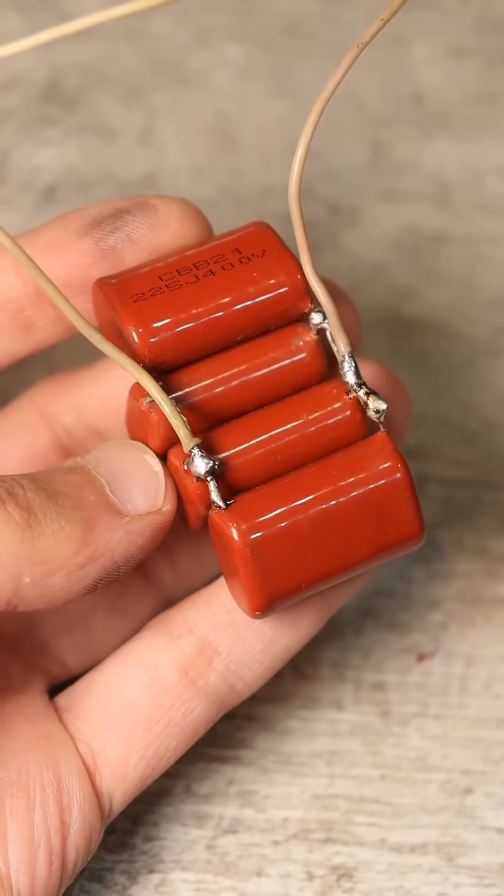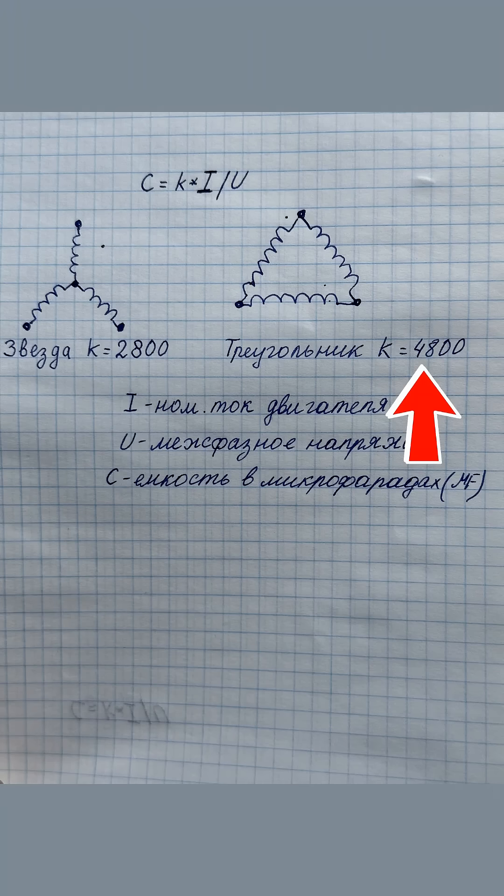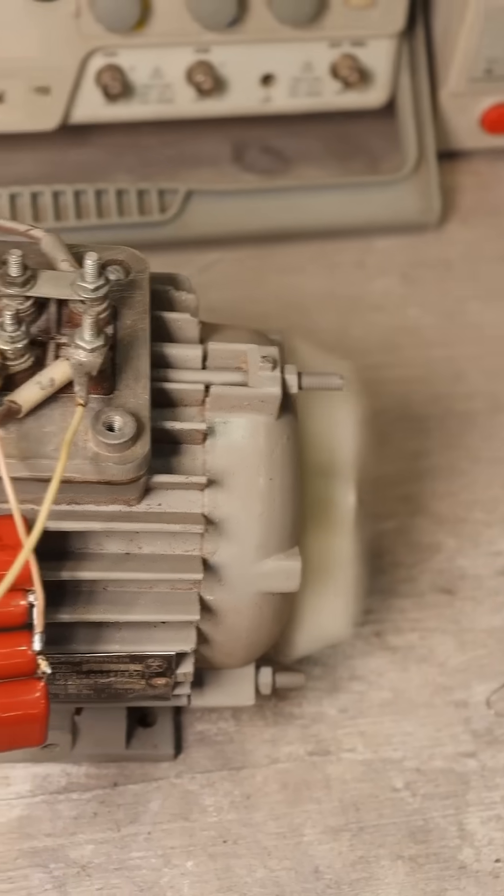The capacity of the running capacitor is calculated using the specified formula where k, the coefficient, has a value of 2800 for star and 4800 for delta, along with the rated current of the motor in amps. The phase voltage in our case is 220 volts.